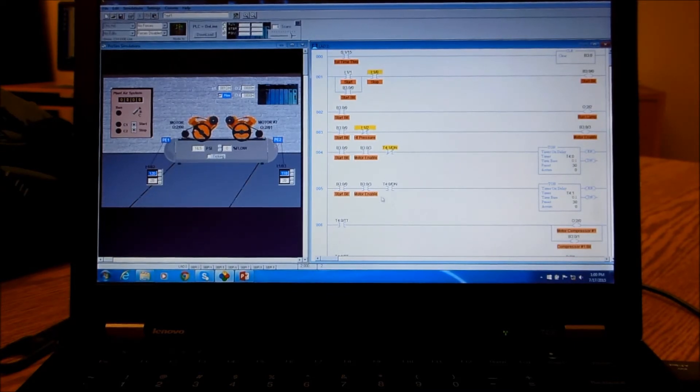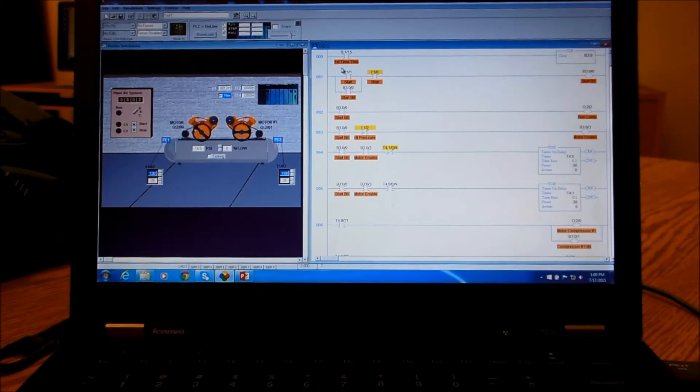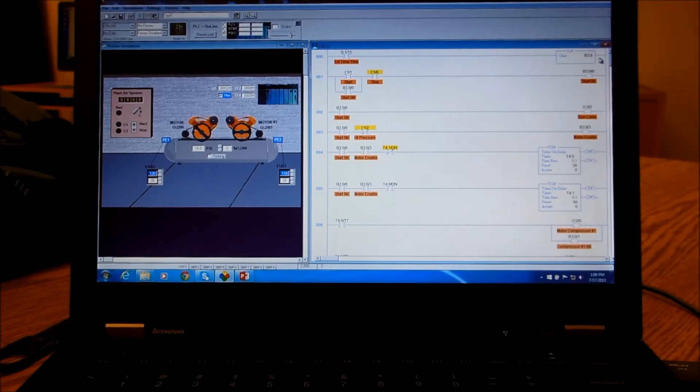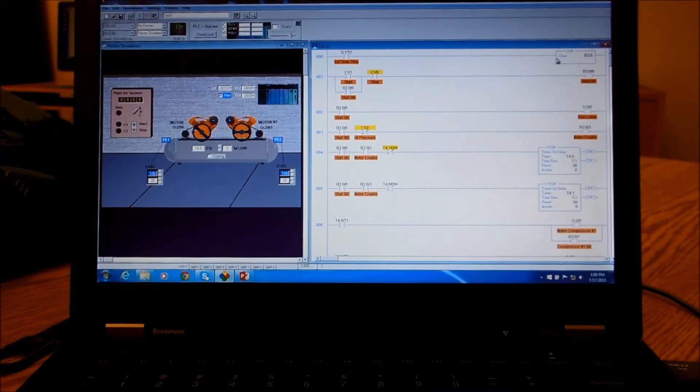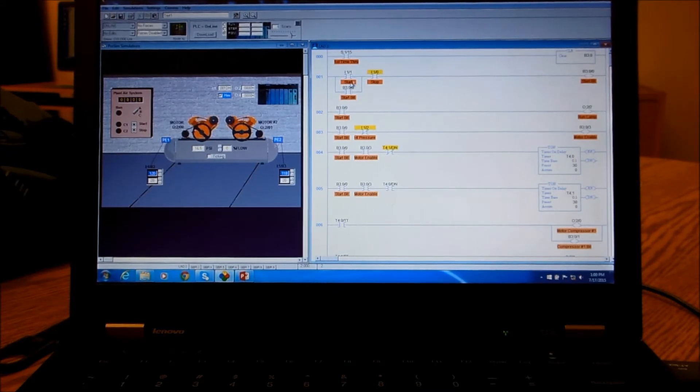There's not rung comments which we should have, but anyway, what we do is we take the first time through bit to clear all the internal bits. I found that's a good idea anytime you're doing a program—just clear all the internal bits and you can start with a known state.